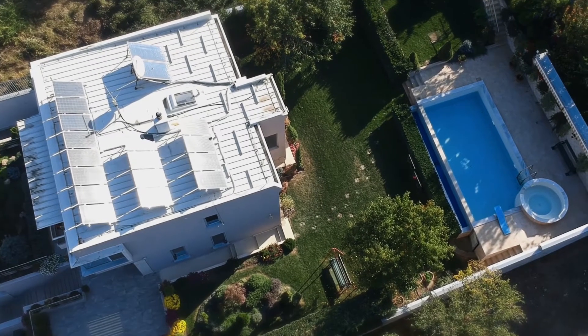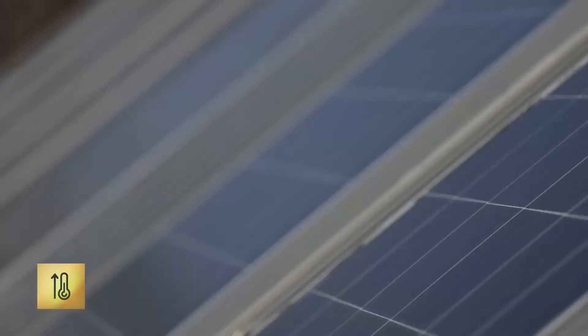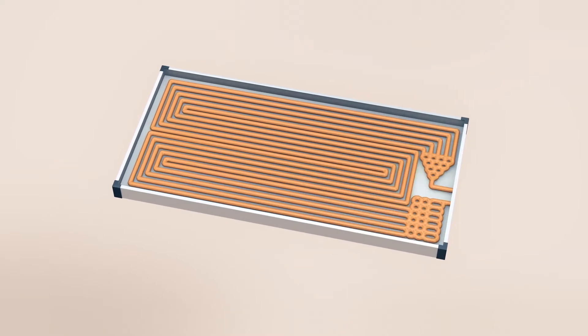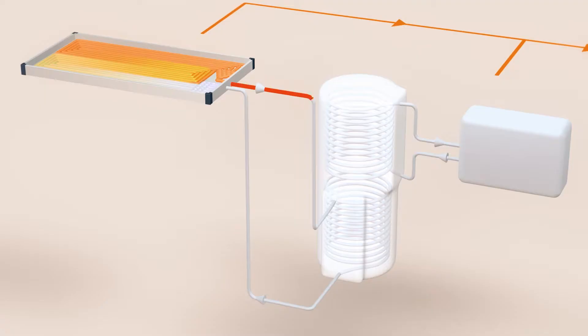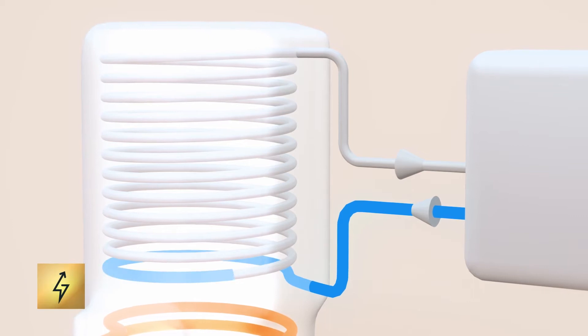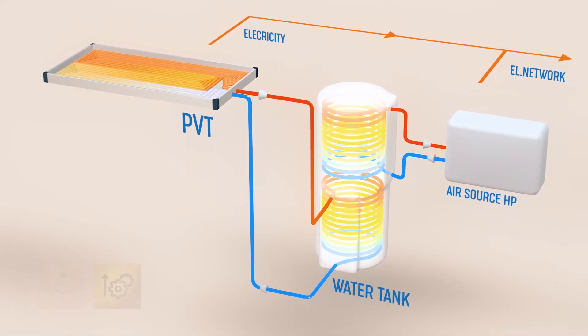One of the biggest problems in reducing the efficiency of PV panels is the increase of temperature during power generation, which in the summer can reach up to 25%. This problem is solved by cooling the PV cells with circulating water through the absorber on the backside of the PV panel, thus heating the circulating water for sanitary or space heating purposes, increasing electricity production, and extending the exploitation period of the panel due to lower working temperatures.